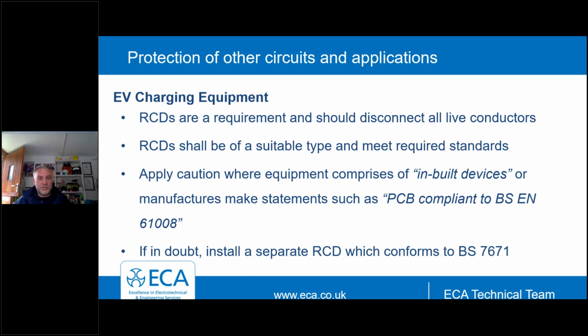A lot of manufacturers who manufacture EV chargers will use an equivalent or a built-in or a PCB type RCD. And it's come to light that not all of them will meet the necessary standards in full. If you don't meet the standard in full, you're not meeting the standard. So it's wrong of us to say it's only met in parts. So if you're in doubt when you're selecting built-in RCDs to equipment, contact the manufacturer and ask for the conformity and if they do comply. And if you feel they don't, it's perfectly fine to fit your own RCD for protection, one which does conform to the British standards and will operate safely. So we've dived into that before with a great webinar. If you've not caught up on that, I recommend that you do.